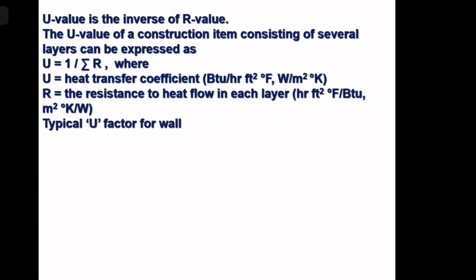Typical U value factor for wall. Let us see. You consider a wall, Indian wall. What do we have? Outside air film. That also offers a boundary layer, which acts as an insulation, which acts as a resistance to heat flow. So thermal resistance of that is 0.044. We have taken this 0.044 from ASHRAE, or ISHRAE also has this value in their handbooks. So resistance of outside air. Next.